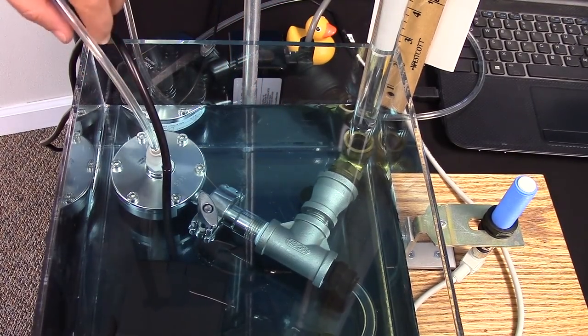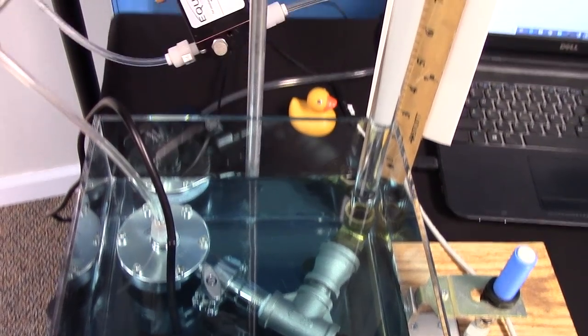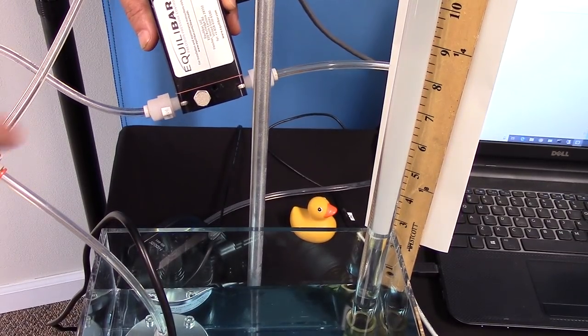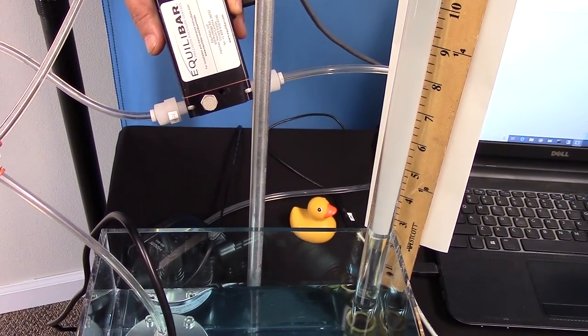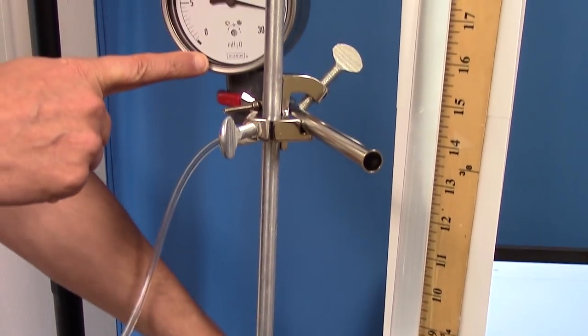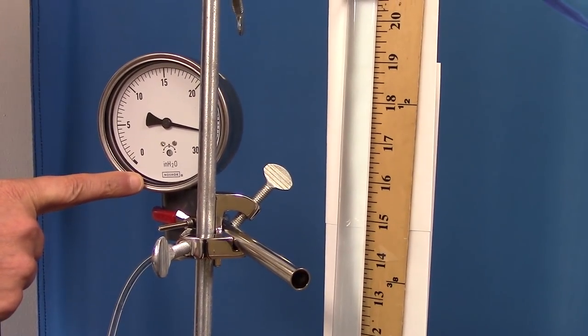The back pressure regulator is controlled by air pilot pressure. We're providing that air pilot pressure with an electronic pressure regulator, and the electronic pressure regulator's pilot pressure is going to be displayed on this gauge, which conveniently for our demonstration is shown in inches of water column.